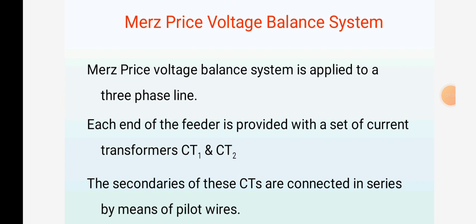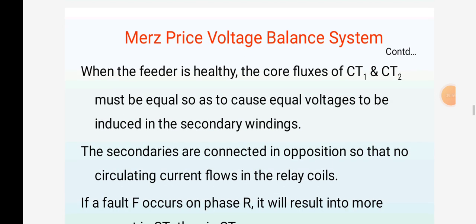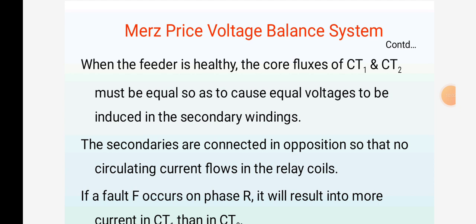The secondaries of these CTs are connected in series by means of pilot wires. When the feeder is healthy, the core fluxes of CT1 and CT2 must be equal so as to cause equal voltages to be induced in the secondary windings. The secondaries are connected in opposition so that no circulating current flows in the relay coils. If a fault F occurs on phase R, it will result in more current in CT1 than in CT2.